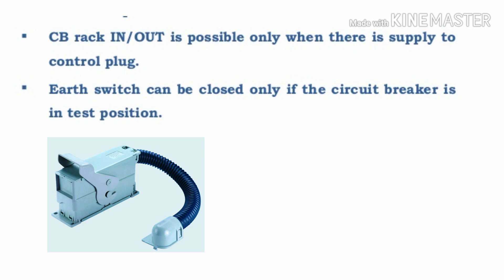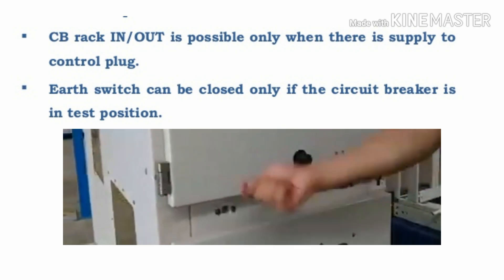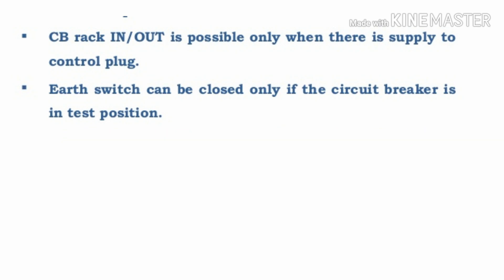The third interlock: circuit breaker rack in and rack out is possible only when there is supply to the control plug. This is the control supply for VCB — once the supply is available only then we can do the rack in and rack out. Rack in is clockwise and rack out is anti-clockwise.